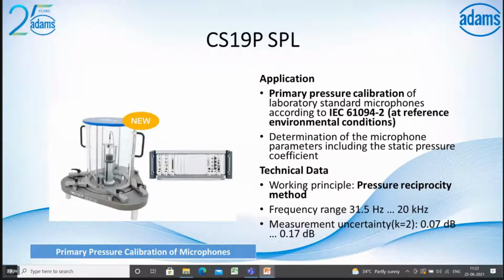So the principle is based on reciprocity. This is specially developed for the high fidelity measurement microphones by using the pressure reciprocity calibration method. During the calibration, we have to use two microphones connected at each end in a closed cylindrical cavity. So how will the calibration be performed?